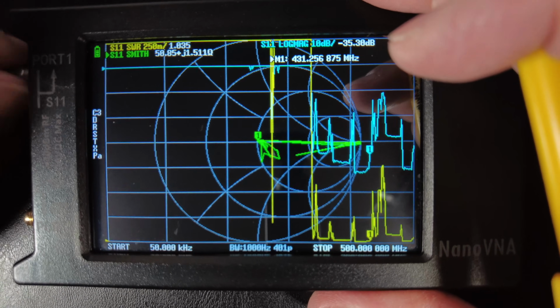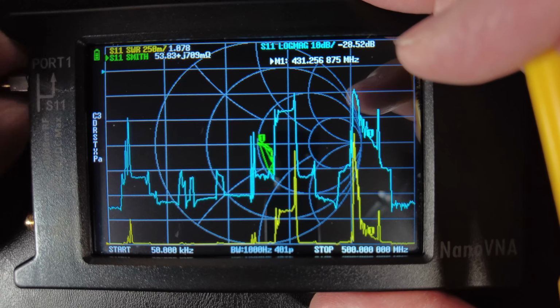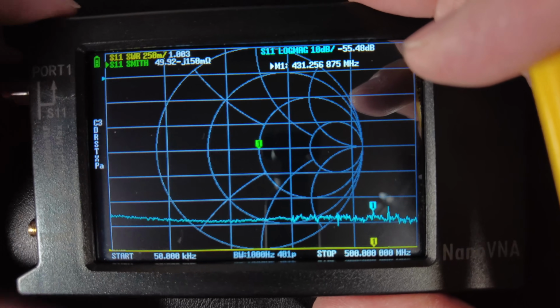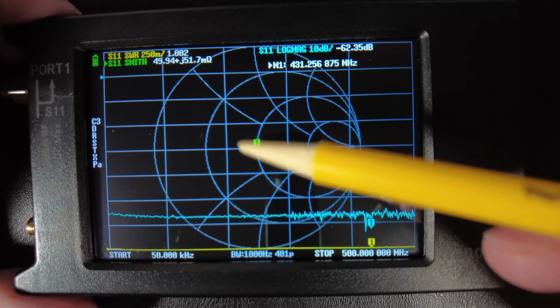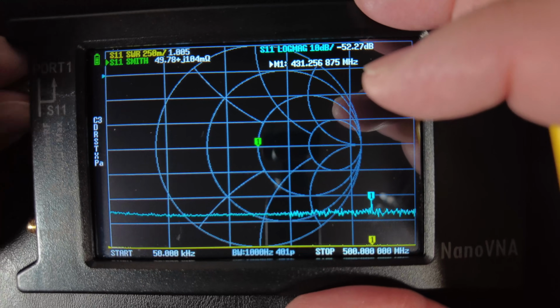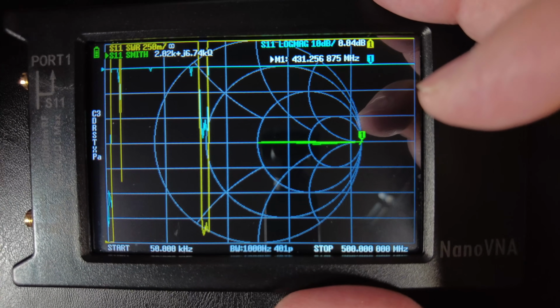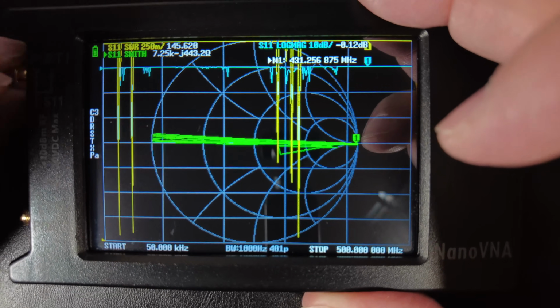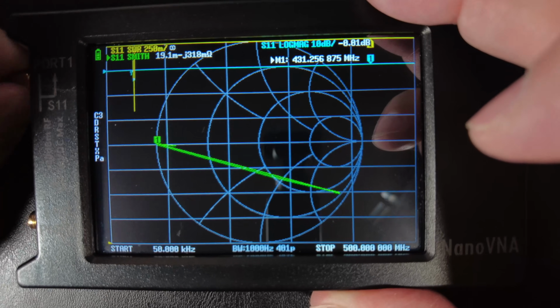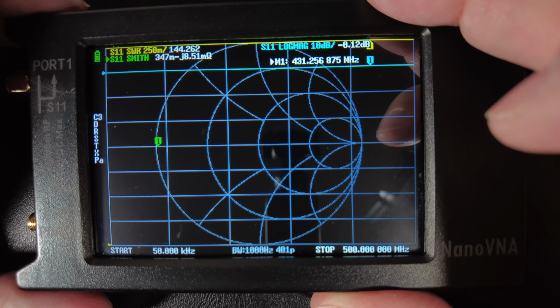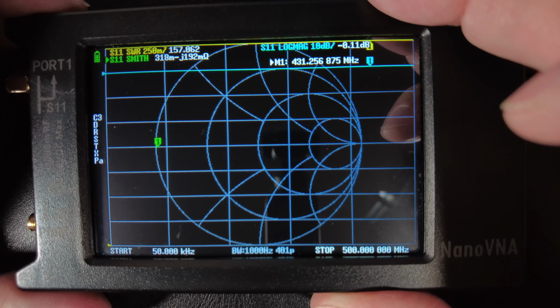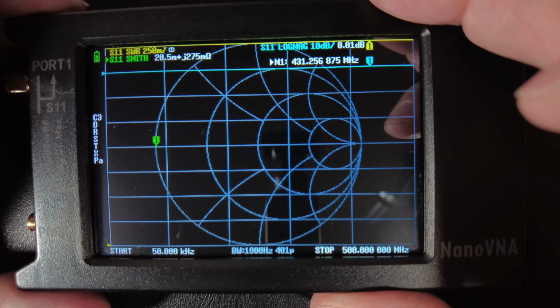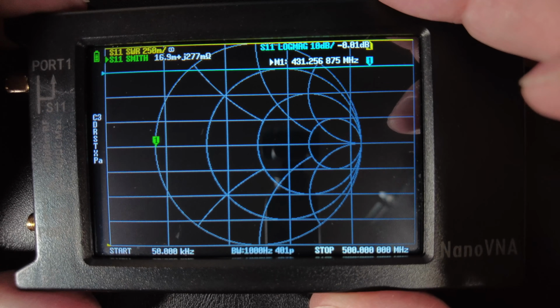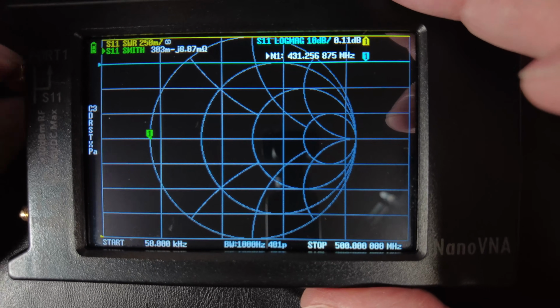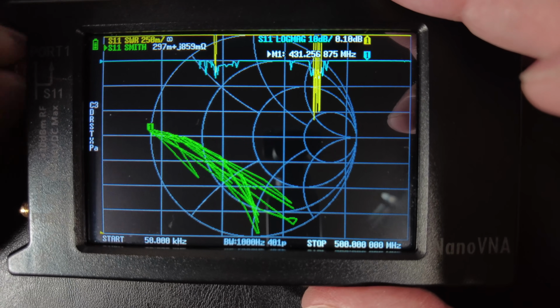dummy load real quick. So with the 50 ohm load attached, there it is. The marker's right in the center. That's 50 ohms. Okay, and the short. And now the short, the marker's all the way over on the left side. So now if you do your calibration and you test that and that doesn't happen, one of those doesn't land where you would expect it, I would just redo the calibration again. But normally if you've done the calibration correctly, it'll just wind up that they'll land in the correct spots.